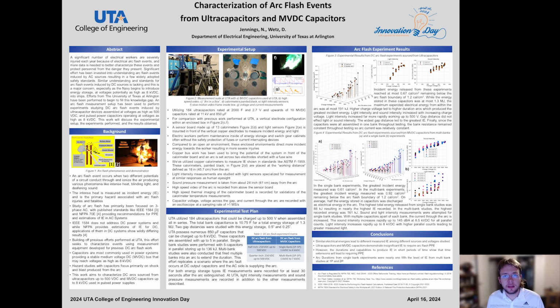As a result, the arc voltage, or the capacitor bank voltage, is also dropping at the same time, and so you have another drop in voltage, just natural from the arc instant energy. And so that is also resulting in a loss of voltage, which could be an explanation for why we see such lower energies released, but we have much greater energy stored.